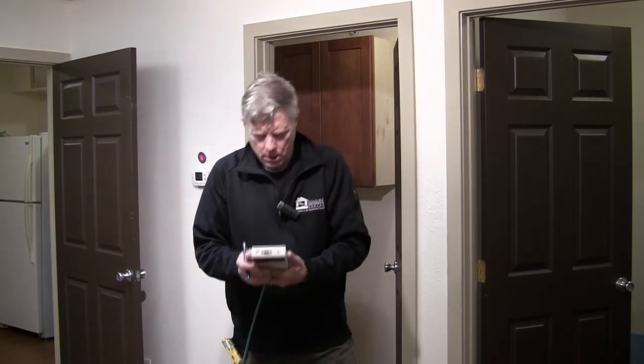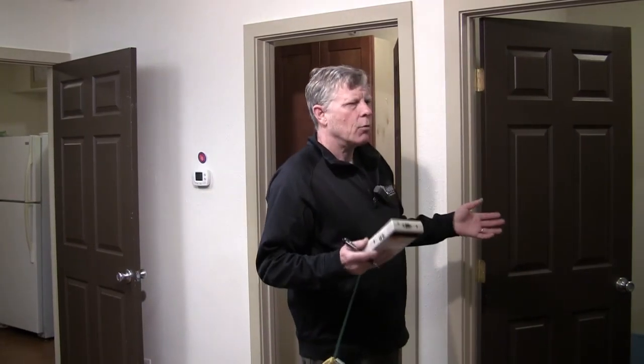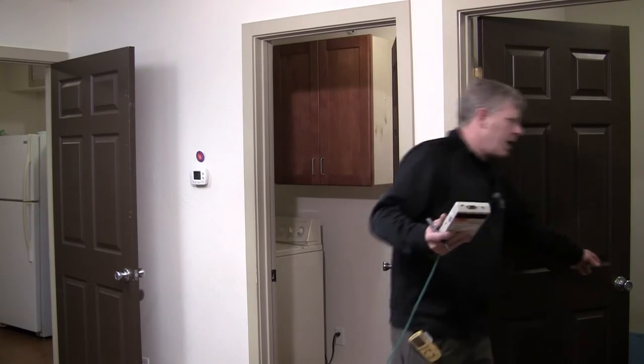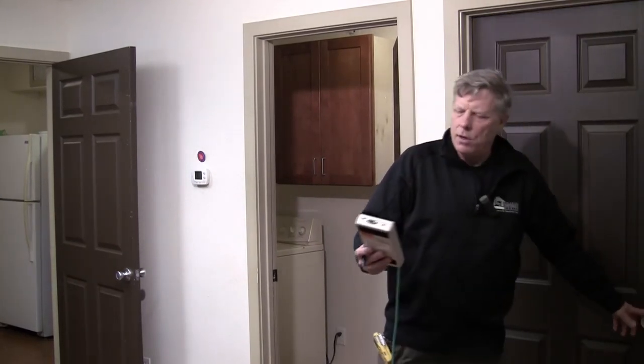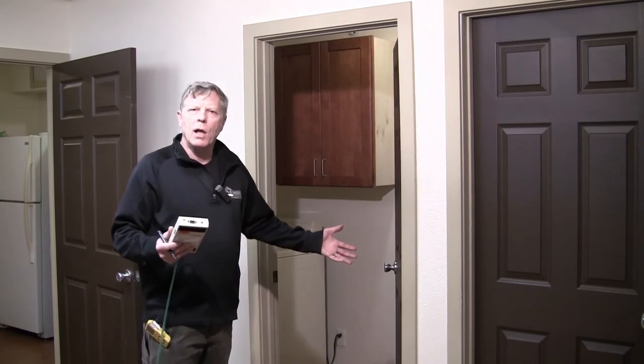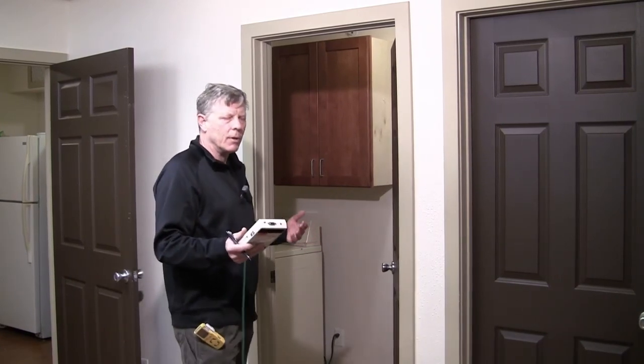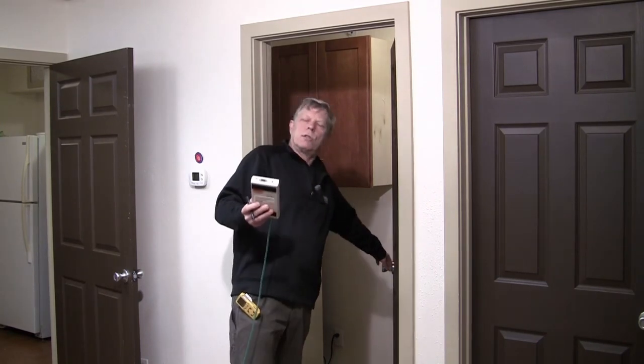Okay, the air handler's on. And it is roughly negative 7.5. Alright, that's quite a jump from negative 3.2. Now, we're going to check our doors. Behind this door is just a supply duct, so my guess is that if I close this, it's going to go to negative, okay, so roughly negative 7.6. Behind here we have a supply plus some exhaust equipment, so I don't really know what's going to happen when I close this door.